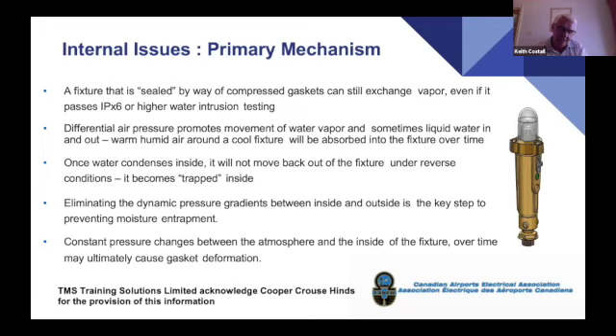And what's happening is that all our light fixtures, whether it's an inset light or an elevated light, are sealed using some form of gasket. And those gaskets themselves have their criteria of performance. Therefore, if there are temperature changes between externally and internally, and with LEDs the internal temperature is going to be dramatically lower than a tungsten halogen, which we already are aware of, then there's going to be some differences.